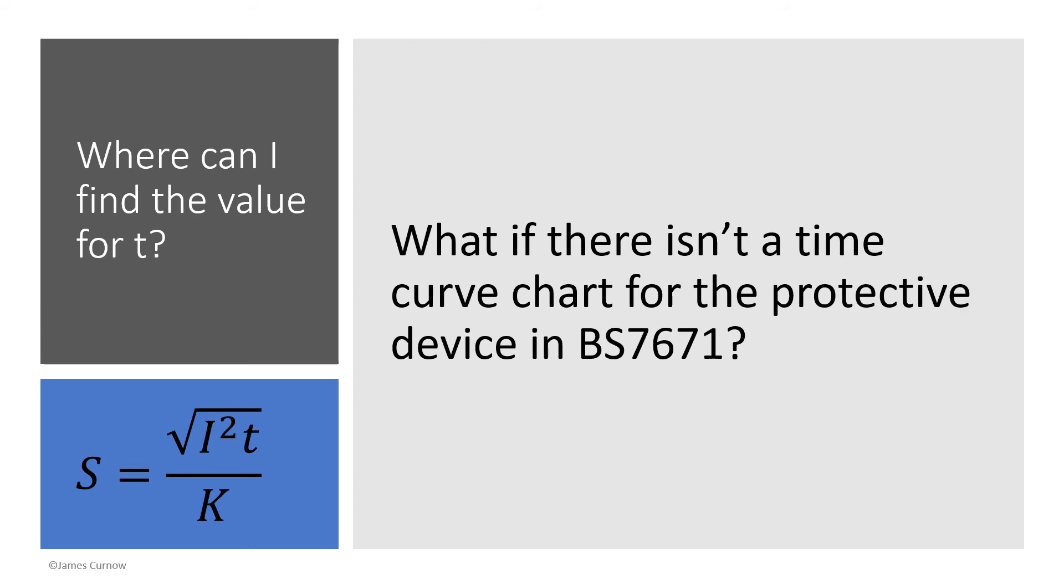For most types of protected device you'll be able to find the time curve characteristics in Appendix 3 of BS 7671. But there are some types of protected devices such as MCCBs or ACBs that aren't listed in BS 7671. In that situation, to find the value for T to carry out the equation, you would contact the manufacturer and request a time curve chart. You would then take the fault current for the circuit and plot it on the manufacturer's time curve chart to find the value for T.